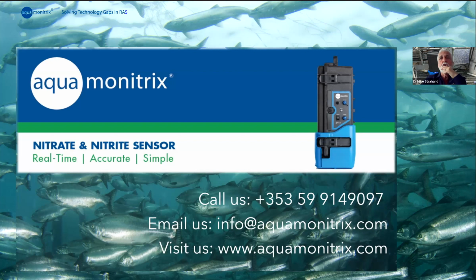The maintenance costs and running costs is a theme which a couple of people have asked about. That is dependent upon your measuring frequency in terms of the cost of consumables. The one consumable is eluent, which is a dilute saltwater solution, relatively low cost. The other consumable would be the column.